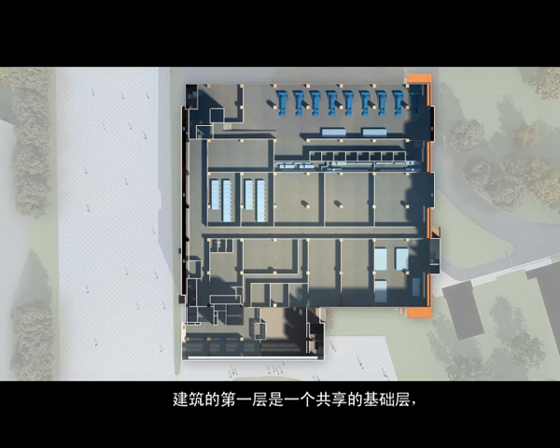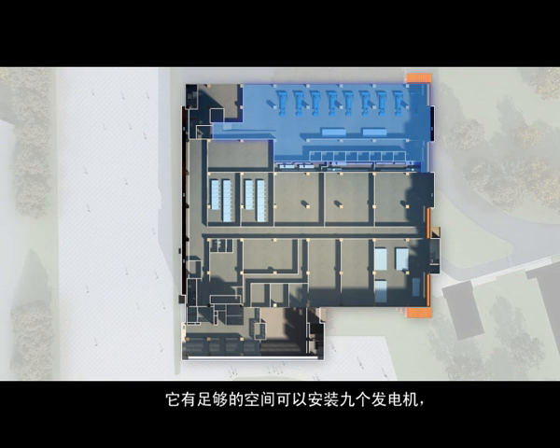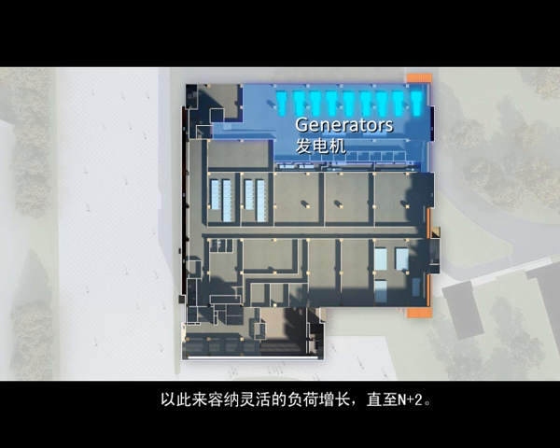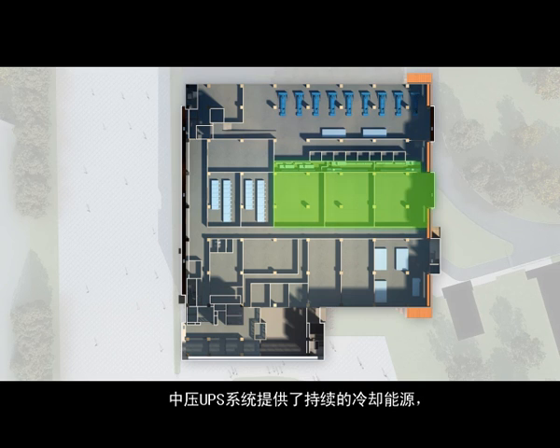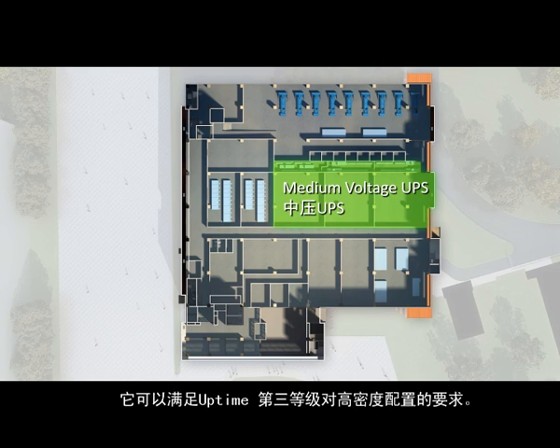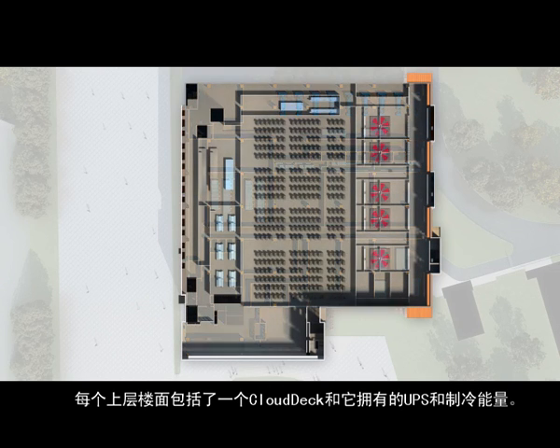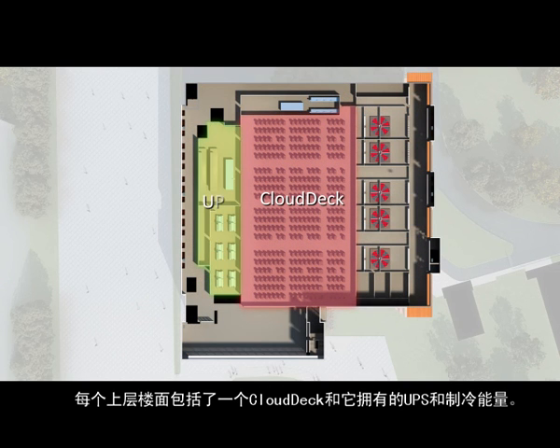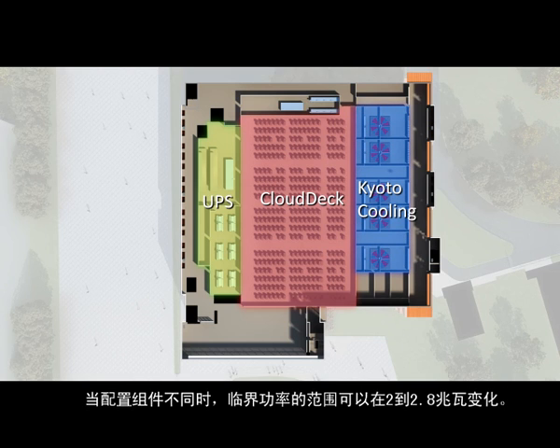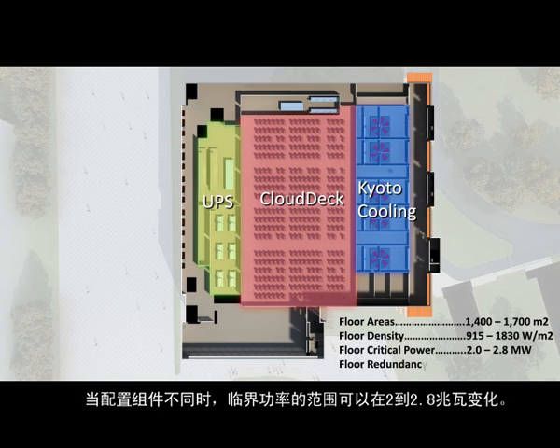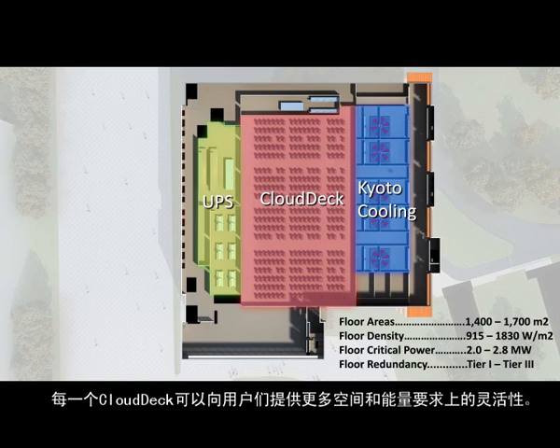The first floor is the shared infrastructure area with sufficient space to install 9 generators, which allows flexible load growth and up to N+2 redundancy. Medium voltage UPS systems provide continuous cooling power availability to meet uptime Tier 3 requirements for higher density configurations. Each upper floor contains a single cloud deck with its own UPS and cooling capacity. With build-out modularity and critical power options ranging from 2 to 2.8 megawatts, each cloud deck provides customers with flexibility for its space and power needs.